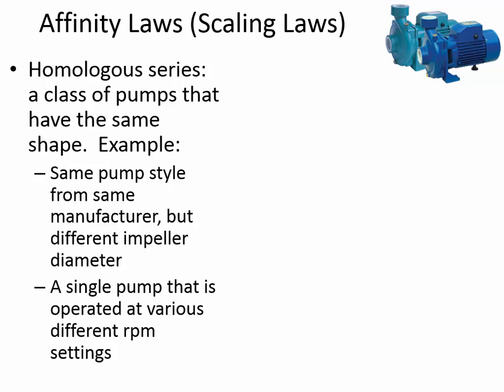And what affinity laws are used for is to describe the situation when a pump is being operated at different conditions than it was originally intended for. Or maybe there could be a pump that has the same shape and the same basic operational parameters, but it's a different diameter. And so here's an example of a certain manufacturer makes a pump in both a 2-inch diameter and a 3-inch diameter. That's the diameter of the discharge hose that would come out of a pump.